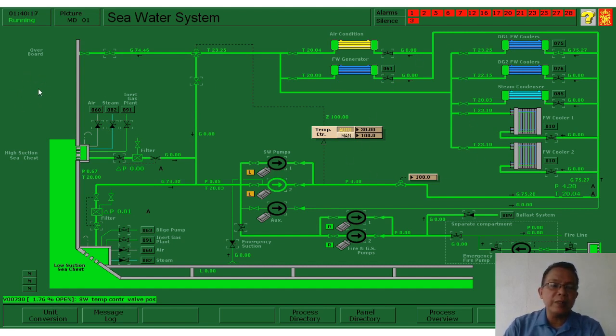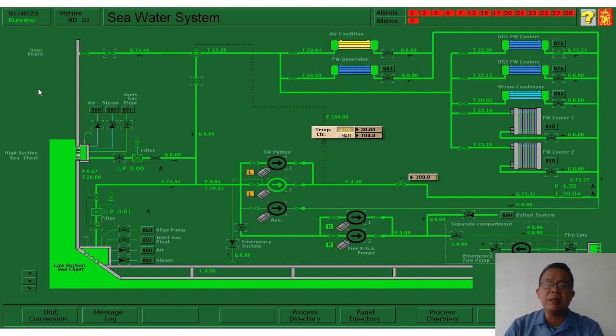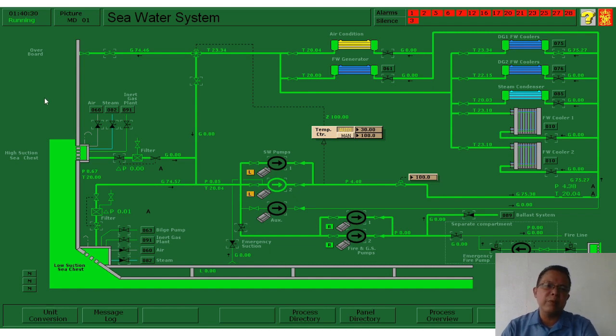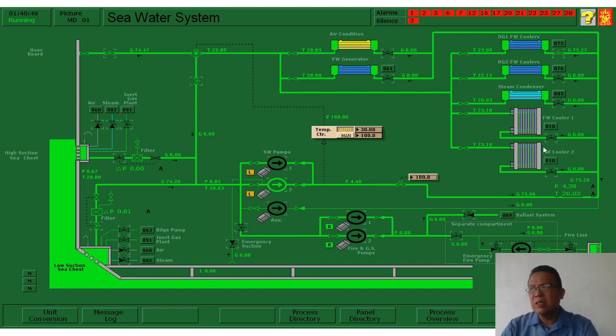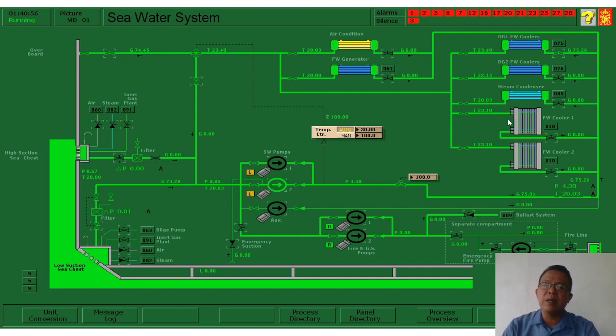Because if the seawater outside is at freezing temperature — like in European countries especially during winter — the seawater in the system is at freezing temperature, and we don't want that because it will affect our jacket cooling. When the jacket cooling temperature goes down, there is what we call thermal shock, which will damage the metals in our system. But we will not allow that because we are engineers, and that is why we maintain the temperatures.